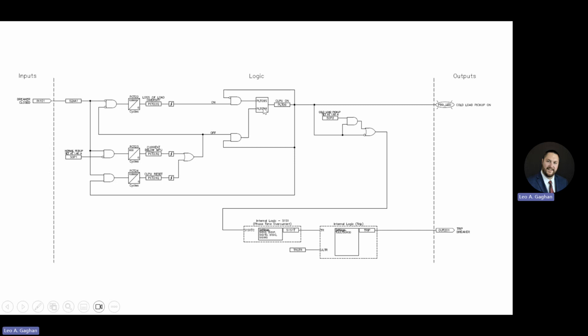Now with it armed, it'll stay armed, and it really won't do anything unless that breaker closes again, because there'll be no current flow if the breaker is open. So the breaker's been open for a long period of time. We've given that load time to get cold, right? Your house has physically gotten cold, let's say. When we go to close that breaker back in, now cold load pickup is on. So we close that breaker in, and we're going to have an immediate spike in current, more current than the normal pickup, let's say.